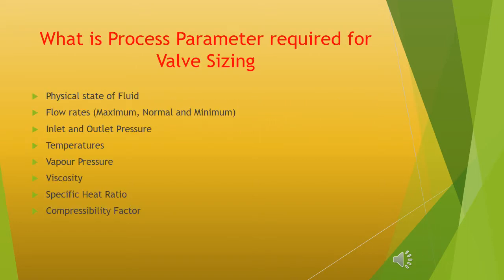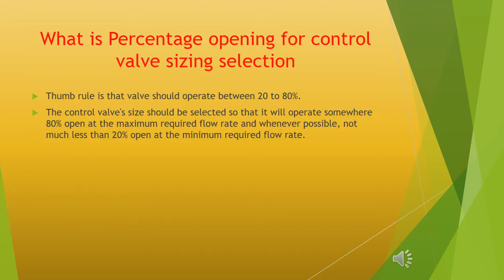What are the process parameters required for valve sizing? The process parameters are: physical state of fluid, flow rates (maximum, normal, and minimum), inlet and outlet pressure, temperatures, vapor pressure, viscosity, specific heat ratio, and compressibility factor.